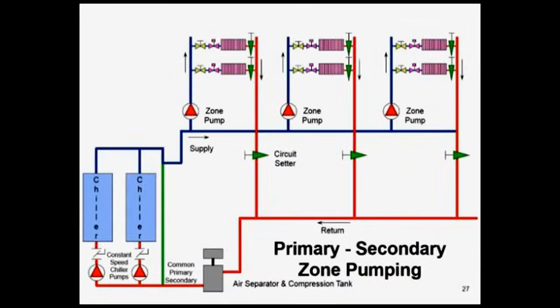Here's a zoned pump. I got rid of the primary pump, and I've got an individual pump in each building pumping the distribution piping out, distribution piping back. This was called zone pumping or distributed pumping. If you go to ASHRAE book, you'll see them in the journals, and they're defined for you. I'm asking you, before you try to balance a building, to sit down and make this simple system sketch to know what the intent is of the design. Otherwise, there's no way you'll ever get this thing balanced properly.